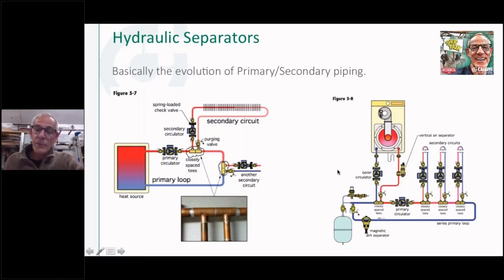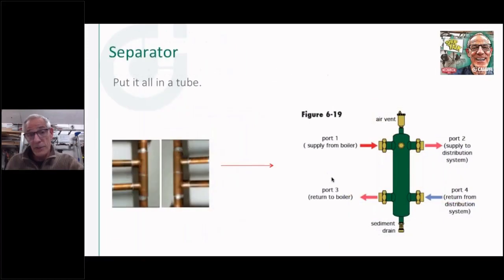So about this time, and I would say this is going back maybe 15 years, is when we started hearing about this thing called a hydraulic separator, or low loss header was another word for it, hydrosep, different names for it. I got introduced to this when I started working with Caleffi, and I think we're one of the pioneers here in the US with this type of device. And if you look at it, if I took two sets of closely spaced T's, smushed them together and put a chamber in the center there, I've actually built this device over here, which is called a hydraulic separator.